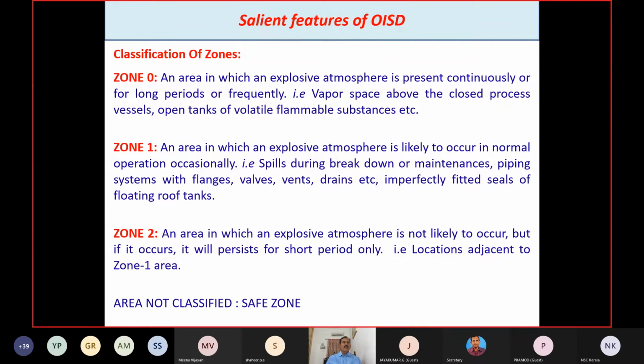And zone 2 is an area in which an explosive atmosphere is not likely to occur, but if it occurs, it will persist for a short period only. An example is locations adjacent to a zone 1 area. Suppose any hydrocarbon is released due to some problem, it will not exist for more than a minute, because it will get dissipated with the air due to wind direction, below its LEL limit.